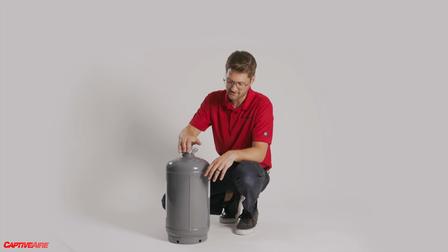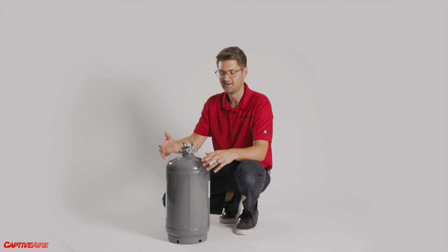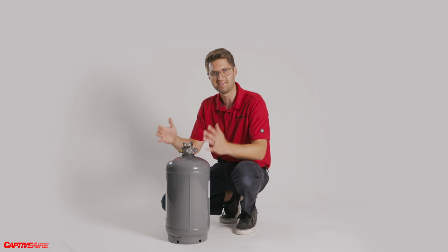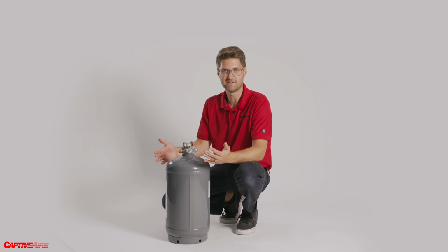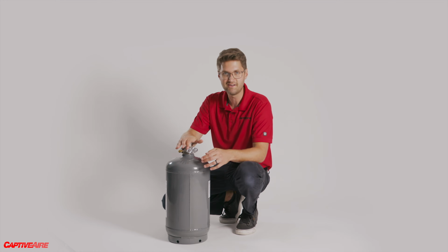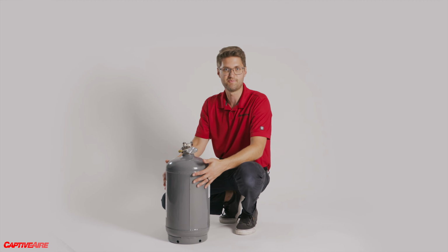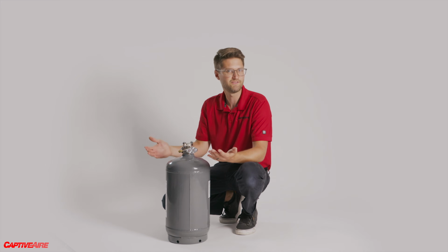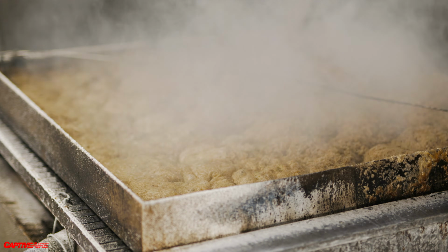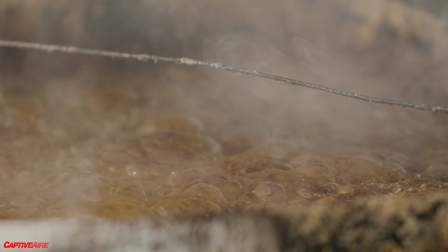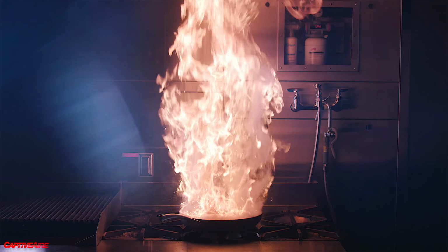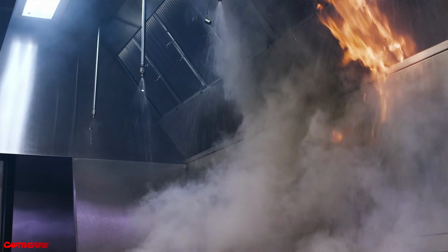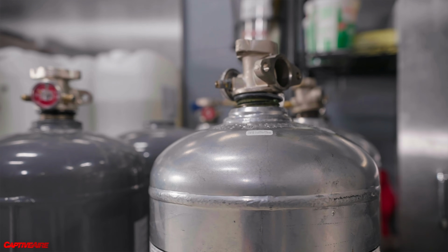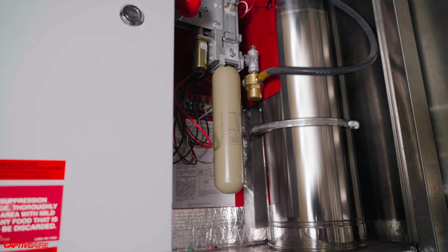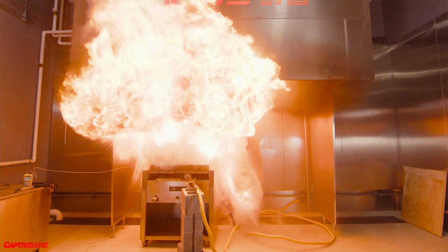Here we have a tank housing the wet chemical agent, and this is basically the downfall of wet chemical systems - there's a limited, fixed amount of agent to put out a fire. So what happens if something goes wrong, like a hole in the saponification layer breaks open and the fire reignites? The worst case scenario is you have a fire situation and don't have enough agent - you only have what's in that tank. There are things that can go wrong.